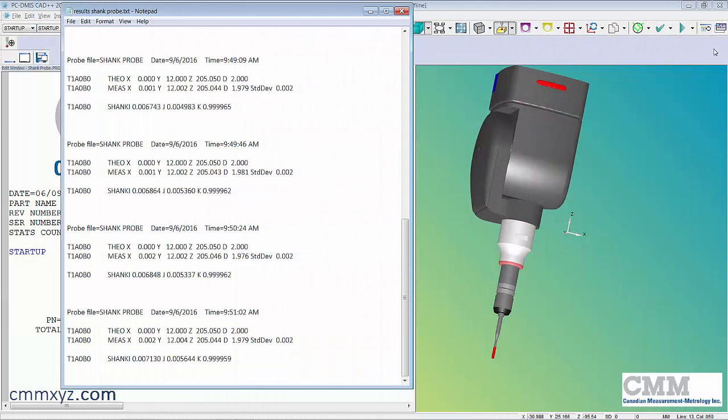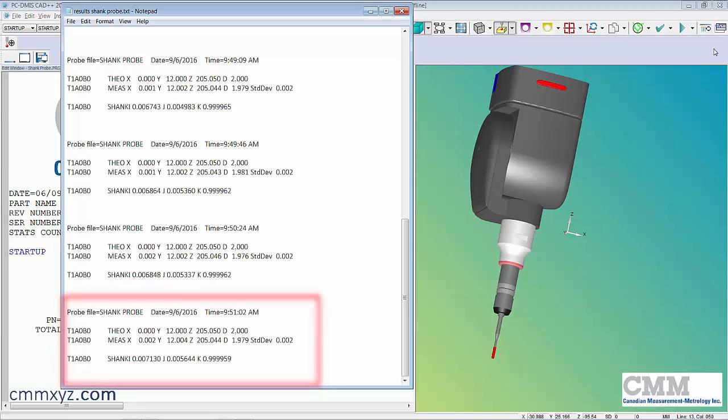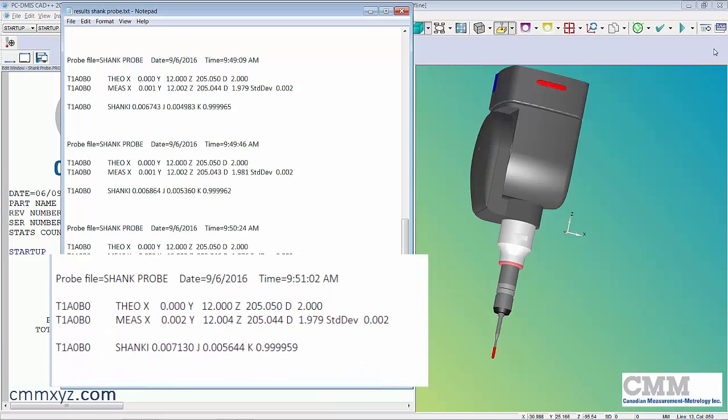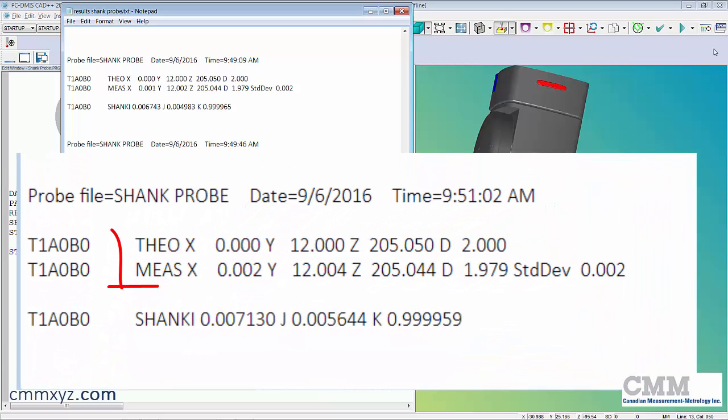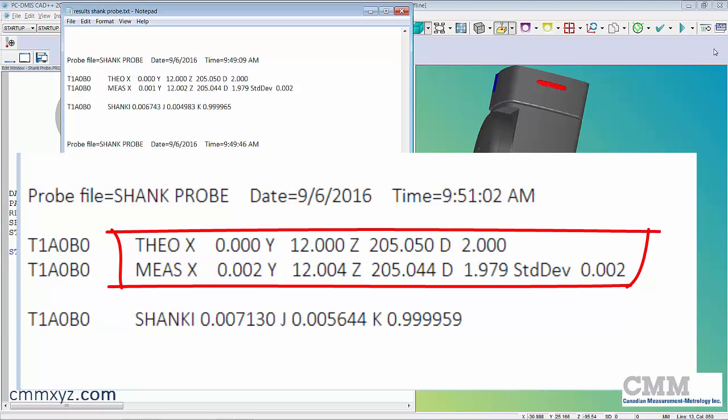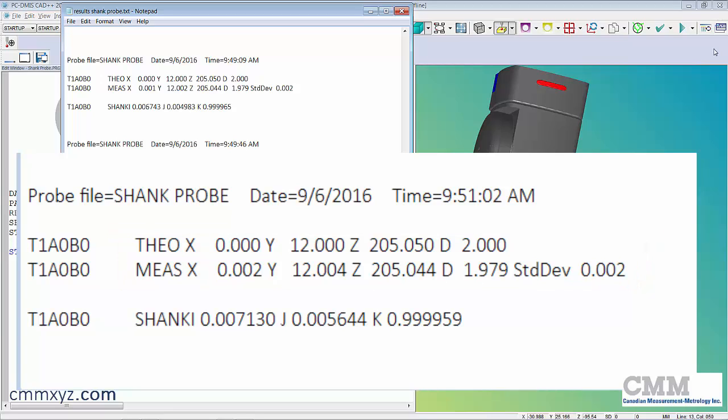Let's have a look at the results of our shank probe qualification. You can see down at the bottom here the results of my latest one. You can see two sets of results and this is important. The first one is what you normally see when you calibrate a ruby ball: an XYZ offset, a measured diameter, and the standard deviation, in this case two microns.